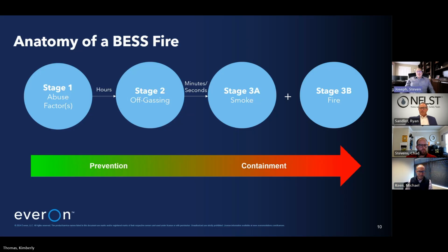Well, I was just going to continue down the stages of development because you have different technologies that are aligned with the stages of development, and so we talked about that prevention stage, right? The technologies that could be applied in the preventative stages to never get to that thermal runaway event or shut things down before it does. But if it does reach that thermal runaway stage, we need that containment portion, right? We need that protection level that, upon reaching thermal runaway, we've got to have listed fire detection technologies such as a listed smoke detector and/or listed radiant energy heat detectors. And those technologies are generally intended to initiate suppression systems where present early on to help mitigate the propagation, of course, that cooling effect to slow down the propagation. And that's really the role of suppression at that particular stage.